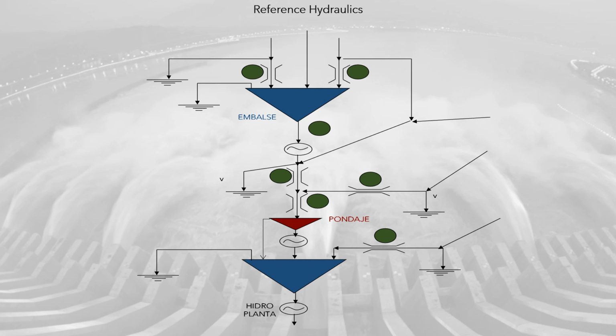Generation units, the effect is summarized in the total or partial unavailability of the generation unit that goes into maintenance, and tanks, the effect is summarized in the loss of the capacity to store water resources during the period of maintenance. Additionally, there may be interaction between the maintenance of elements of different types. This is due to the relationships between the different elements, and the possibility of common resource consumption in maintenance processes. For example, to coordinate the maintenance of a tank, it is necessary to shut down the tank-dependent generation units.